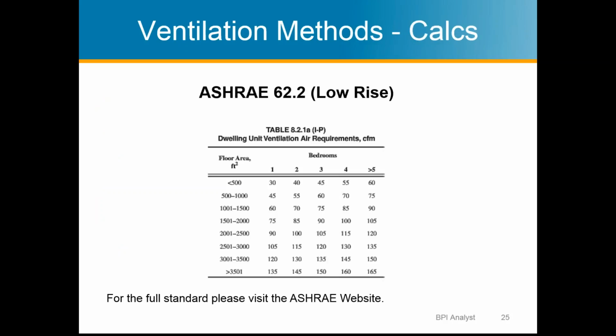The calculation basically stems from ASHRAE 62.2, and there's a chart here saying how much air in CFM, that's cubic feet per minute, would need to come in based on the size of the house and the number of bedrooms. And bedrooms is a proxy for the number of people in the house.